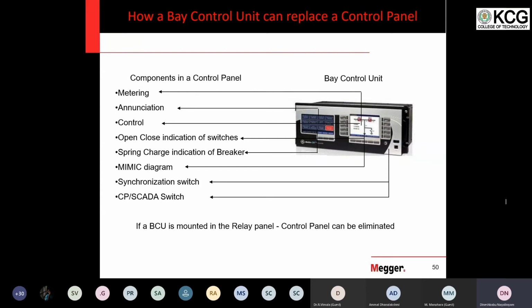The second, the numerical technology: we already saw how fast it will record information and communicate to restore the system back to service. That means when there is a fault and it trips, a control panel only trips and doesn't give any further information because it's electromechanical. No further communication is possible. Whereas a BCU transfers that signal to the load dispatch center, the SCADA operators. So your restoration will be very fast.